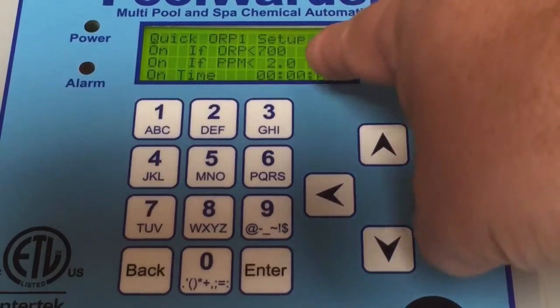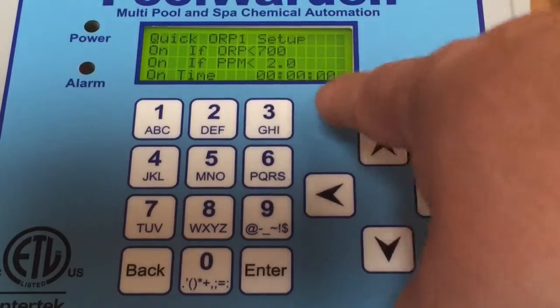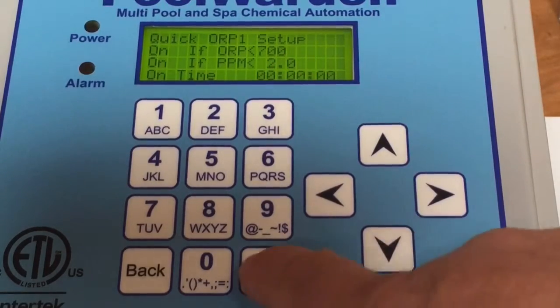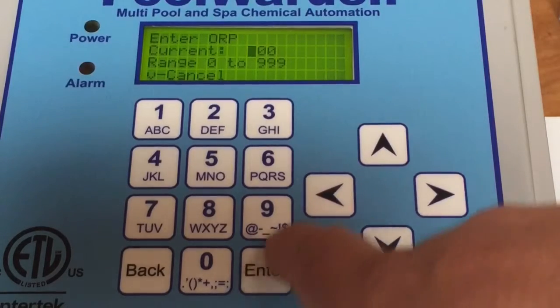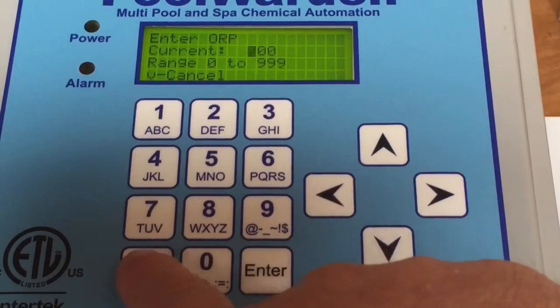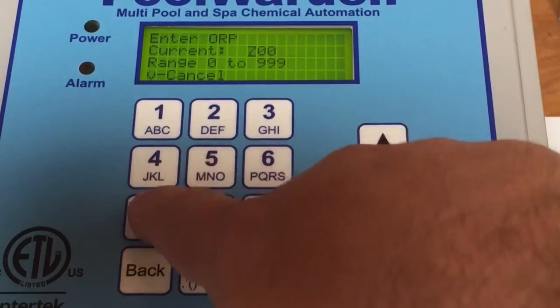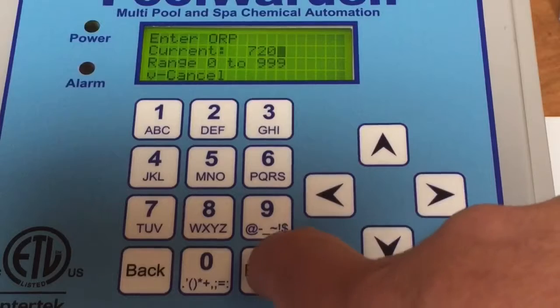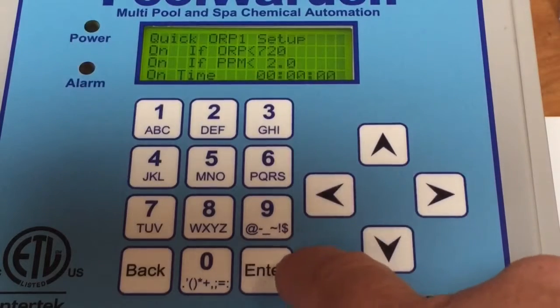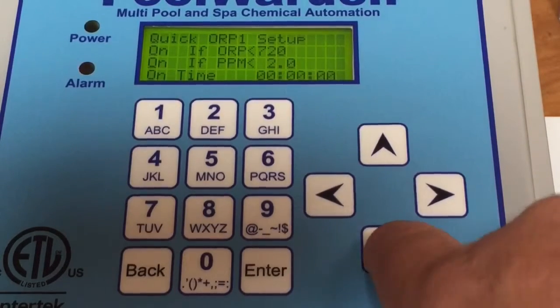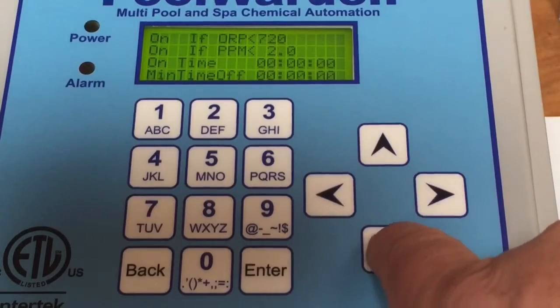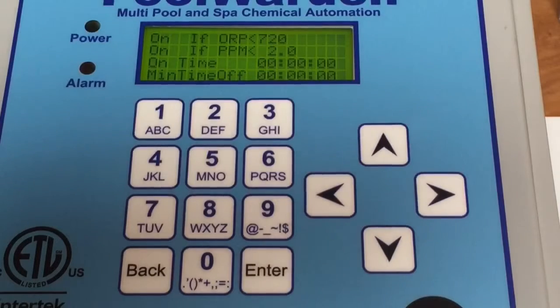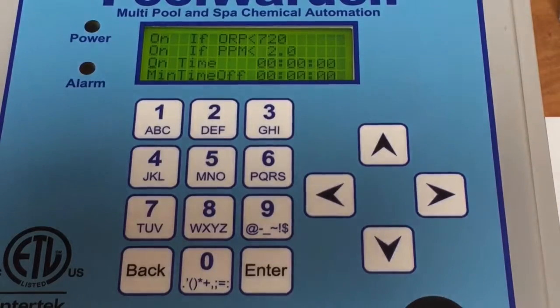You can go here to ORP, push enter, and you can change that to any number you want. Say we want to go to 720, then push enter. It'll also allow us to tweak our on and off times, so you can get real precise on your chemical control, which will help alleviate wasting the chemicals.